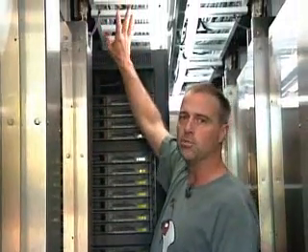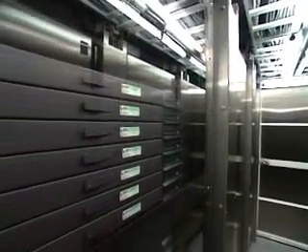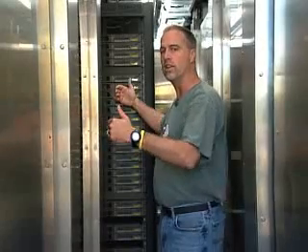You see some of the other flourishes we did that kind of make this a really unique item. A lot of cable management up top — we've paid a lot of attention to how the cables run. You're able to pull a rack out into the aisle and service it with all the power and cabling still intact with the unit running. You'll also see interior lighting, so you can work in here — it'd be pretty dark if we didn't have that. The racks are set at a 90-degree angle, so when they go in, the air is blowing through them down a whole row. In between each rack, you'll see a panel that includes the chiller. Air goes across one rack and immediately through a water-cooled radiator that cools the air before it enters the next rack. Very tightly integrated, very efficient cooling system. All we need on the outside is cold water in, hot water out, and we can cool this whole thing.